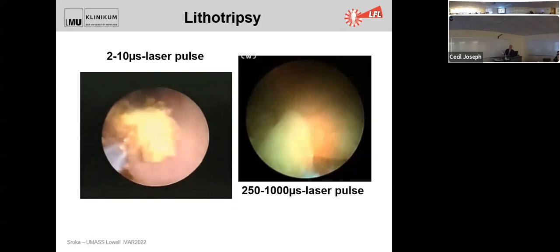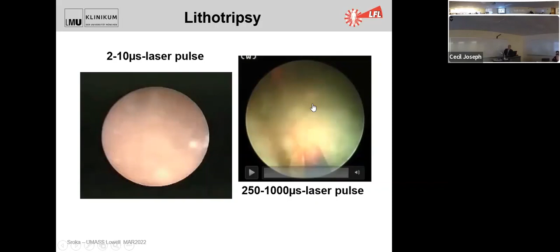Here you can see how it looks when you use laser pulses of 2 to 10 microseconds pulse durations. And this is a fiber, this is a stone in the urethra, and you can see that the stone is jumping around. This is what we call propulsion or retropulsion, depending on the country. And this is not very lucky because the medical doctor needs to chase the stone, and sometimes it's jumping into the kidney in the back, and then they really have trouble finding it in the kidney. If you use pulses which are longer than 250 microseconds and in the milliseconds region, then you can see clearly here the destruction is very, very slow, but the stone stays in this place. There is no chasing. And that is what the medical doctors would like to have.